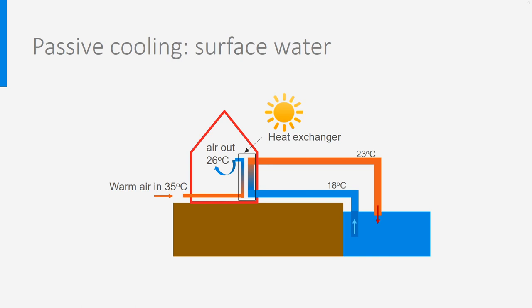In many countries, there are regulations about the maximum temperature at which the water is re-injected into the river, lake or sea. This maximum temperature is around 25 degrees Celsius or even lower, limiting this way the available power. The aim is to protect the fauna and flora in the water, which could be harmed by too high temperatures.